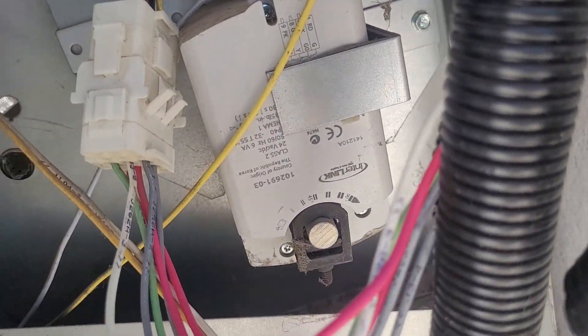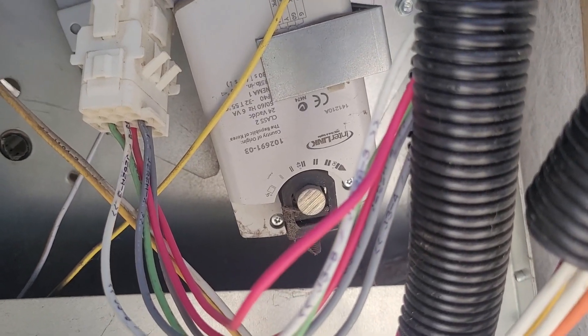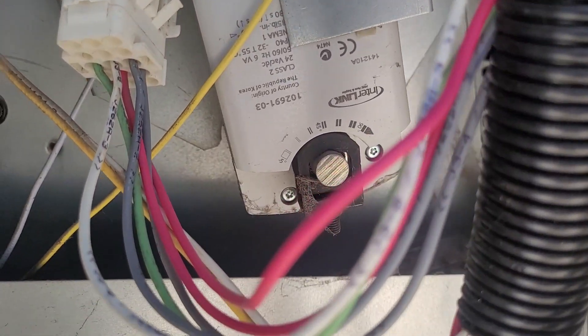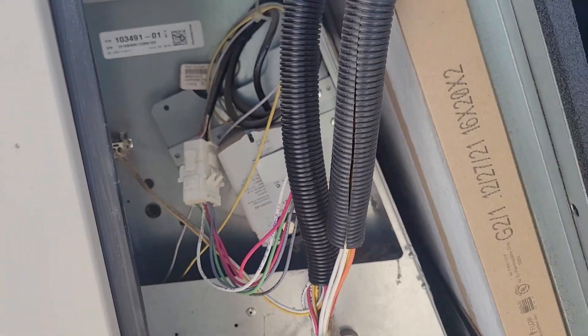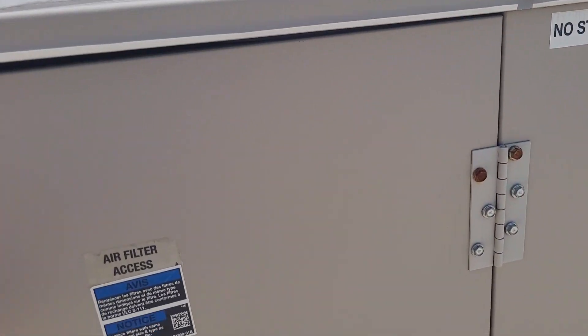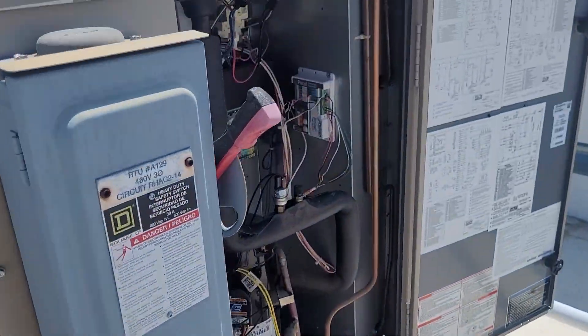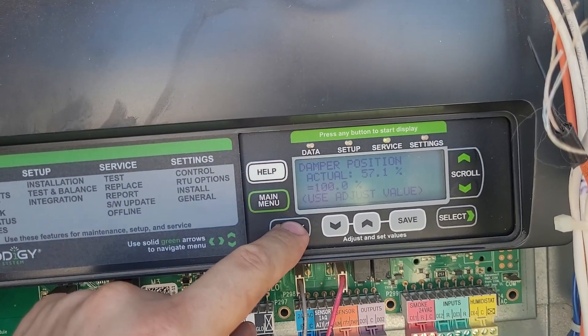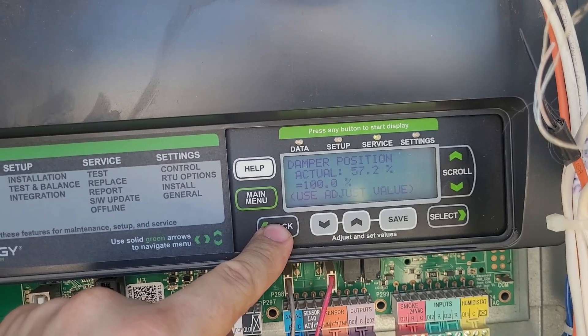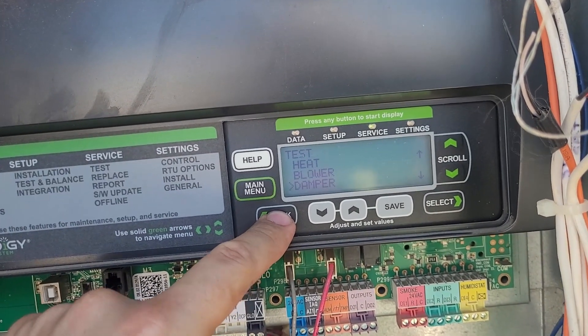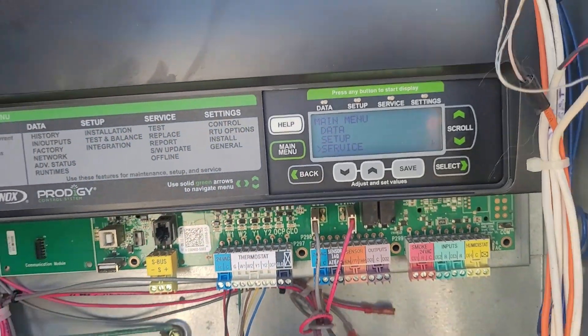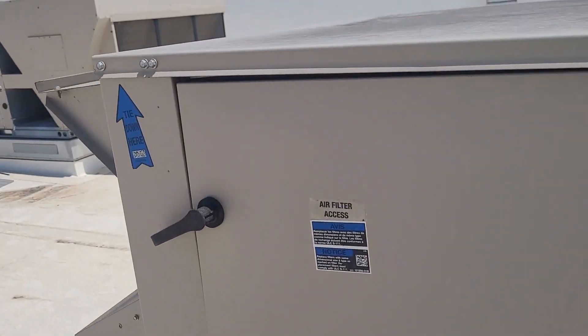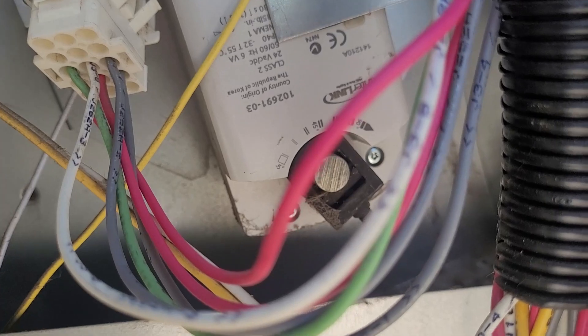Actually, near that clicking — these white motors are notorious for going bad at 50%. You can see that thing is stuck right at 50% and it's not going to go any farther, so this actuator needs to be replaced. That's why we test them. Backing out of the menu — you can see it got to 57% and it's died. Just backing out of the menu is enough, and the economizer actuator should go back and close on its own.